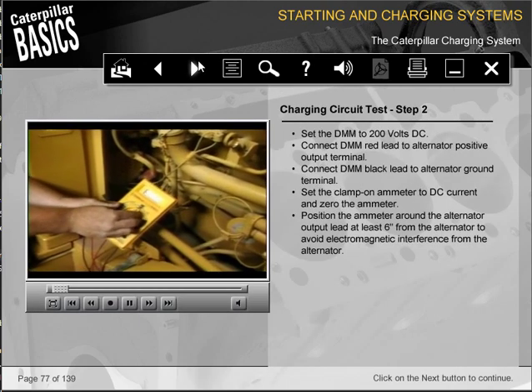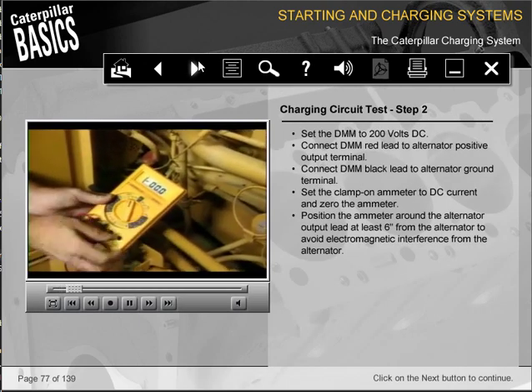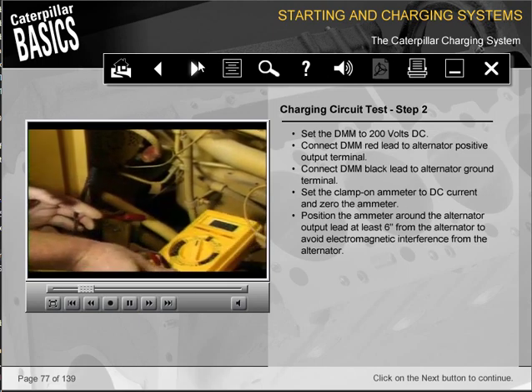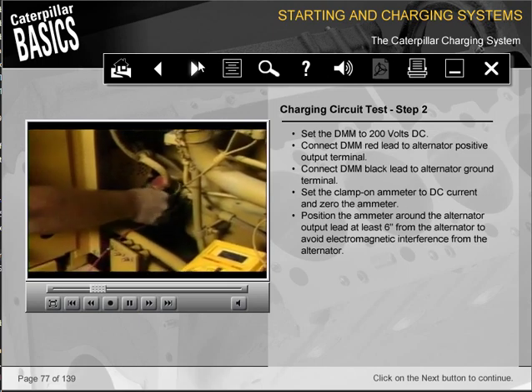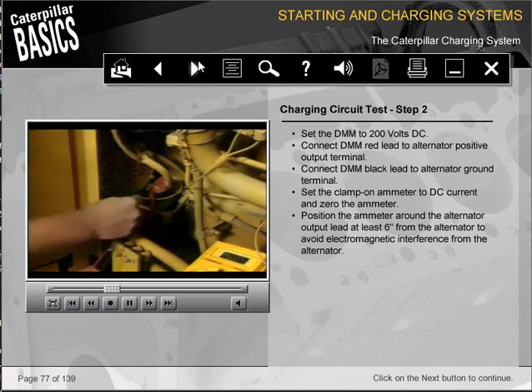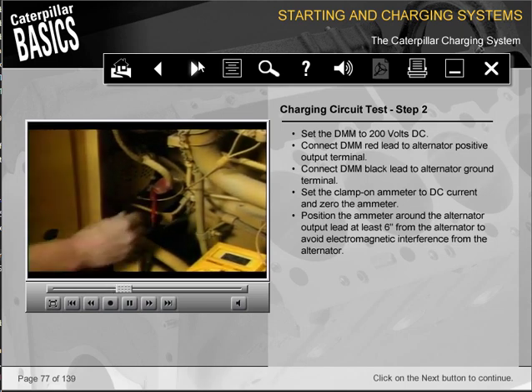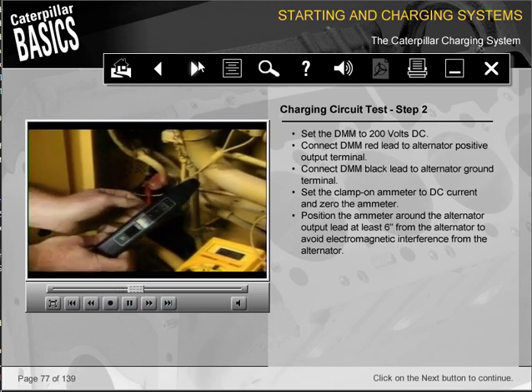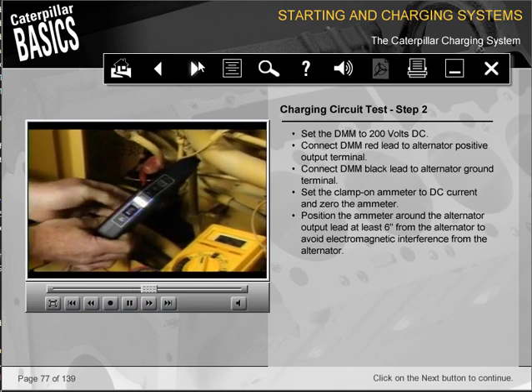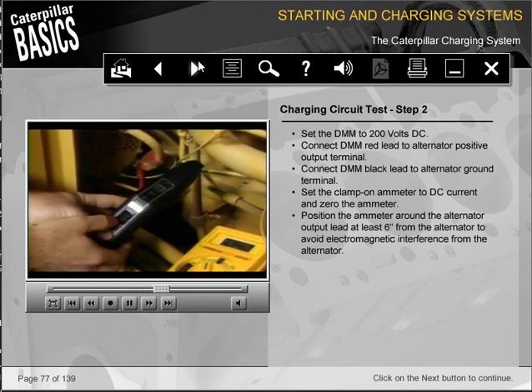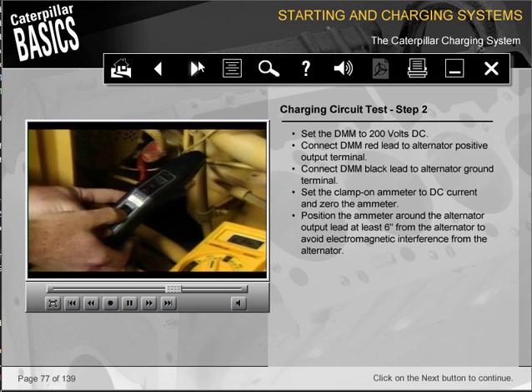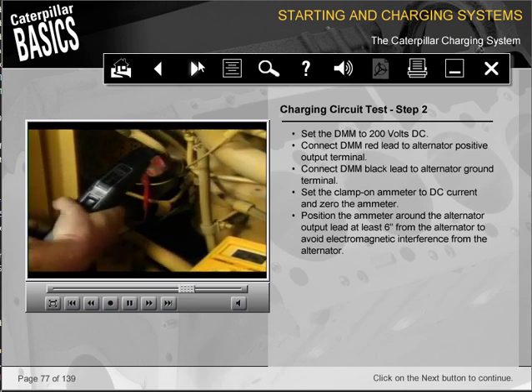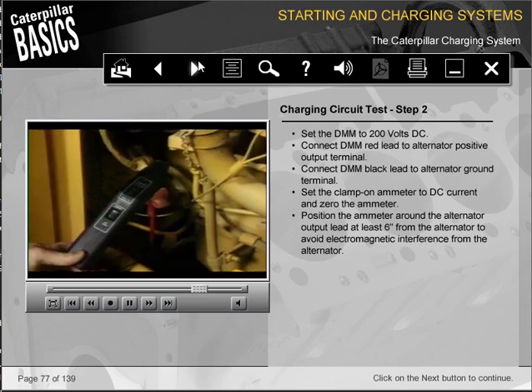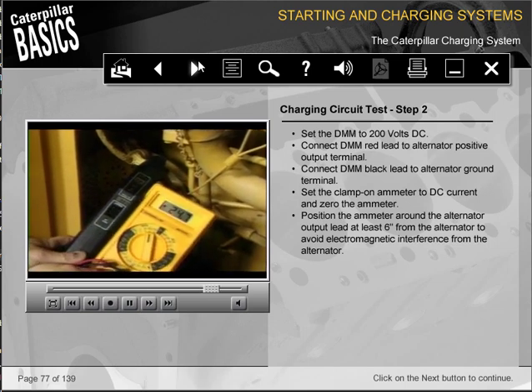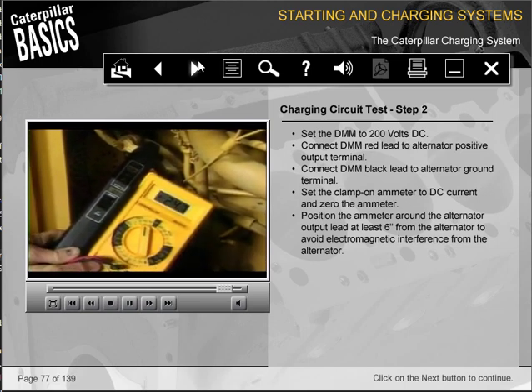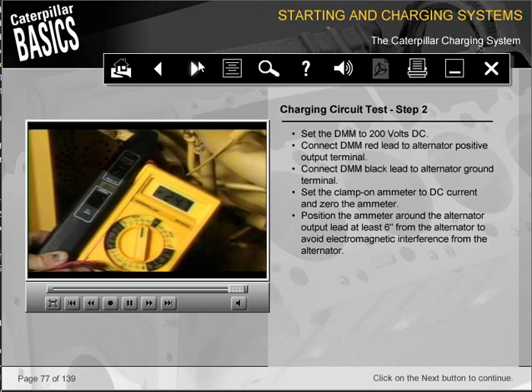Set the DMM to 200 volts DC. Connect DMM red lead to alternator positive output terminal. Connect DMM black lead to alternator ground terminal. Set the clamp-on ammeter to DC current and zero the ammeter. Position the ammeter around the alternator output lead at least 6 inches from the alternator to avoid electromagnetic interference from the alternator.